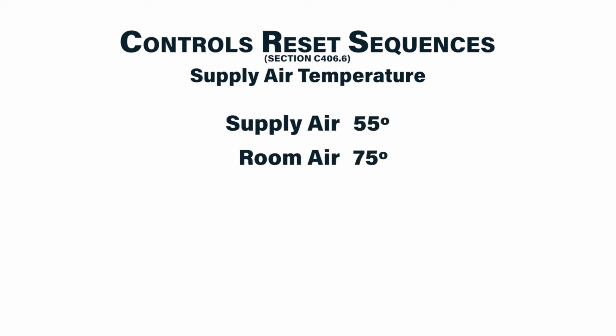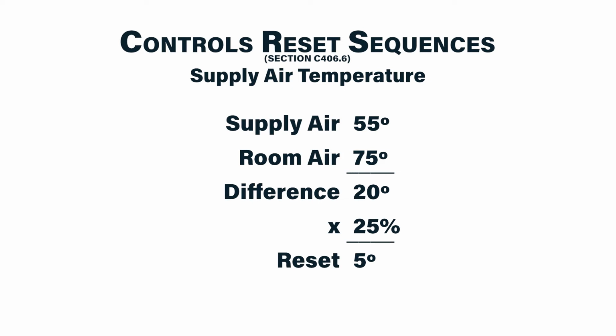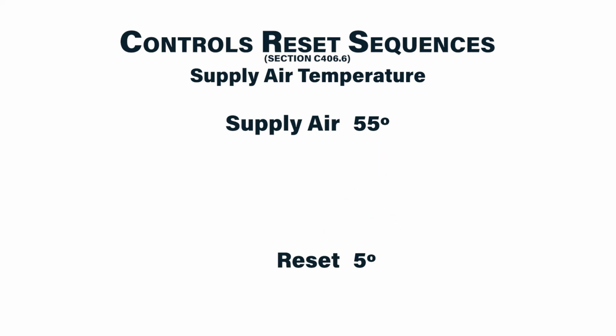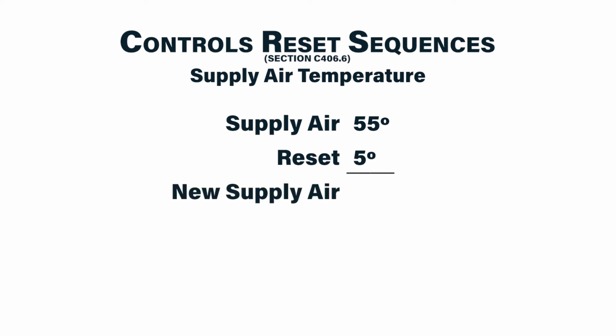So, for example, if the supply air temperature is 55 degrees and the room is at 75 degrees, then the minimum adjustment is 25% of the difference, or a 5-degree reset. If you have a 5-degree reset, this just means that as it gets colder outside, you would reset your supply air temperature up 5 degrees so that you save energy when it's cold out.